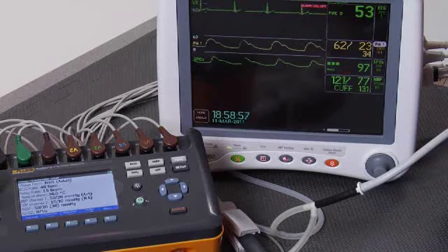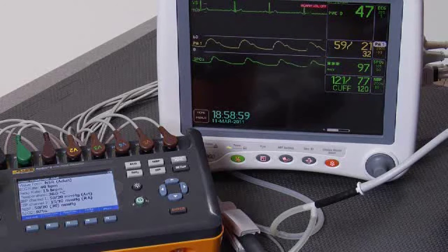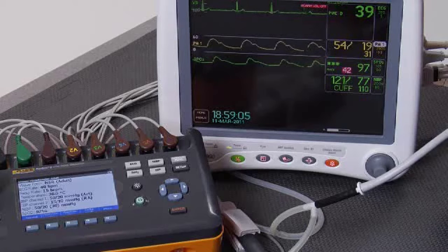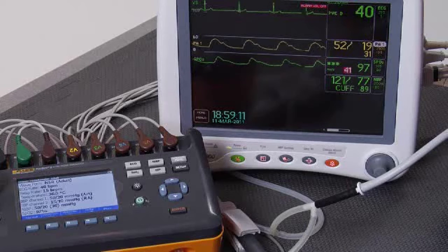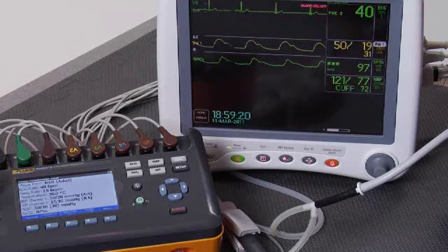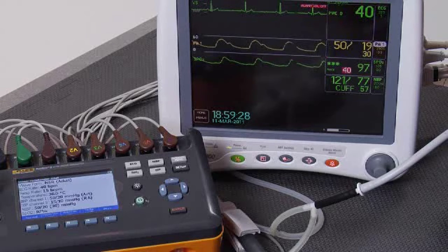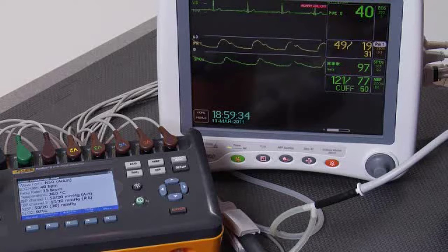We're looking for an ECG rate of 40 beats per minute, respiratory rate of 15 breaths per minute, and invasive blood pressure measurement of 50 over 20, and cuff blood pressure of 50 over 20 with a mean of 30, and an O2 sat of 97%. You can see that the ECG rate on the monitor is already 40. Our invasive blood pressure is 50 over 19, very close to 50 over 20. Our cuff is working on getting its measurement, and the O2 sat is 97, right on with what we asked for, what we're simulating.